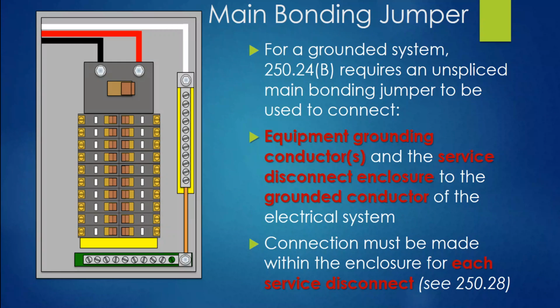Okay. All right, so that's not to say you might not get a preset piece of equipment with a wire type with labels on it that comes from the factory and they've already done all the sizing. That might be the case. But for the most part, if you see a separate wire in here connected to two separate buses, then what they've done is actually size a main bonding jumper here.